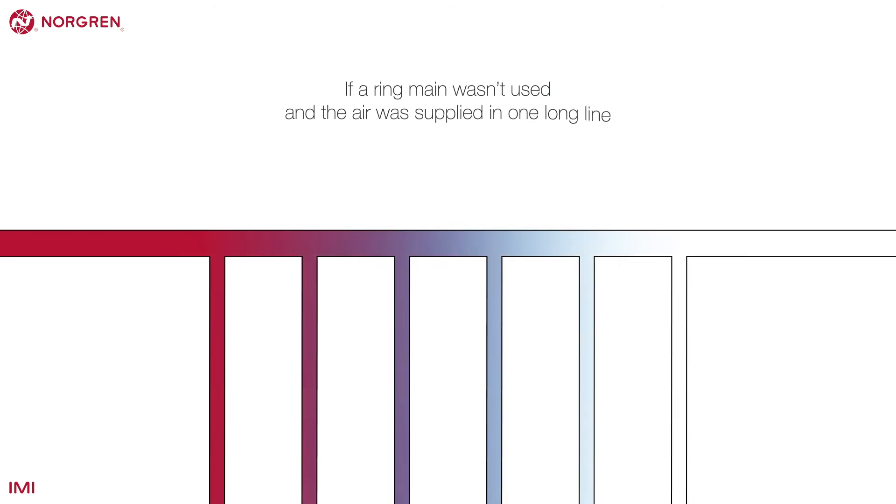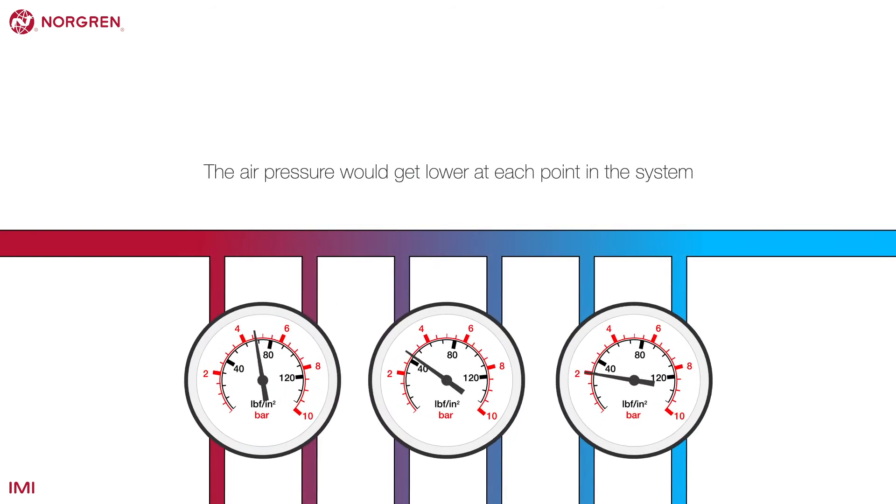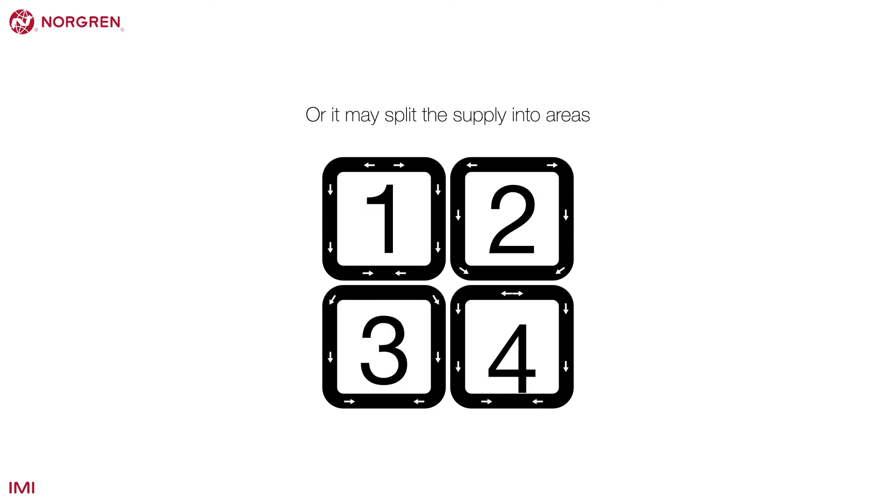If a ring main wasn't used and the air was supplied in one long line, the air pressure would get lower at each point in the system. A factory may have one ring main serving the entire facility or it may split the supply into areas or zones. Each zone would have its own ring main, allowing the air supply to be isolated when not needed.